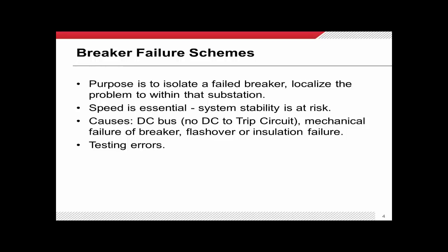Testing errors are a huge problem with breaker failure schemes. And quite a few utilities will go to great lengths in how they design the schemes to make it easy to be tested and safe to be tested. And the example I'm going to give you at the end of this lecture was caused by a testing error. So anyway, another consideration as we go through with this.